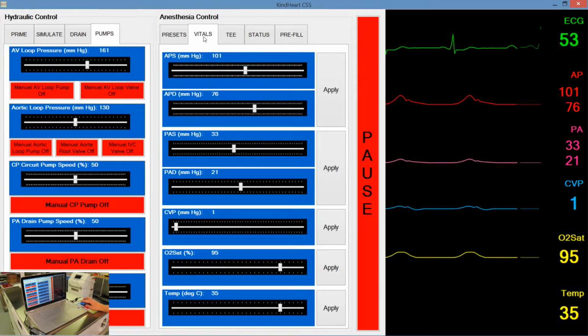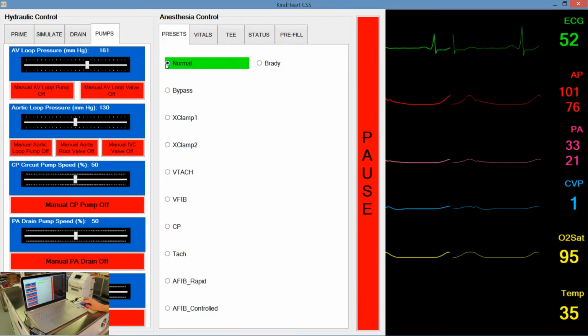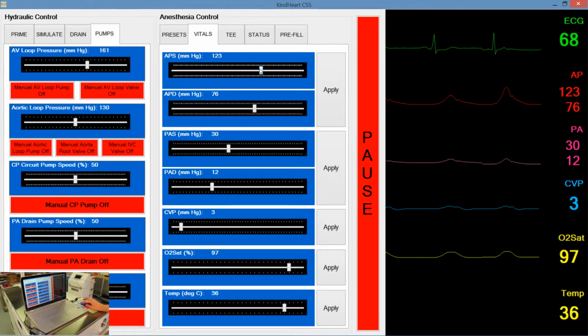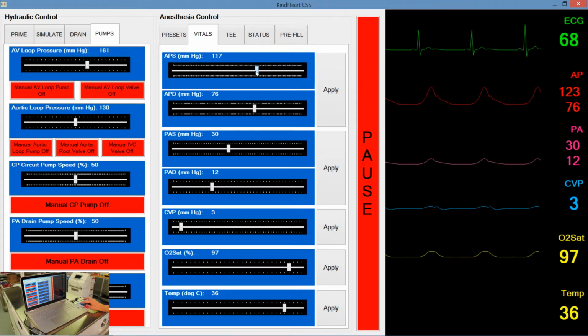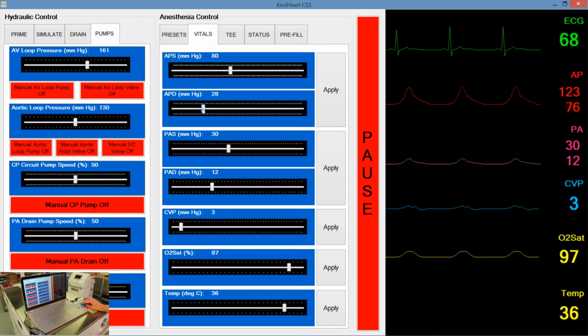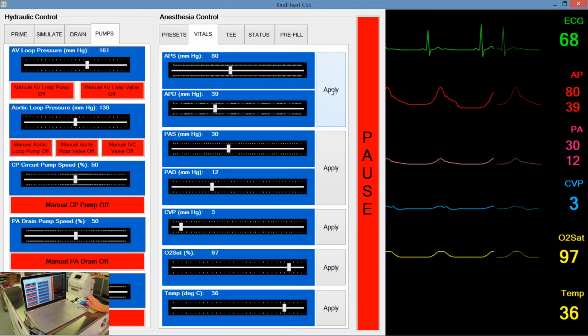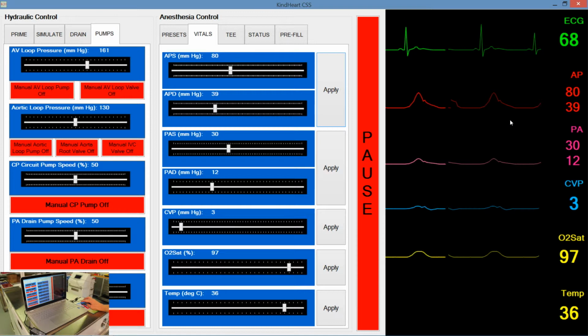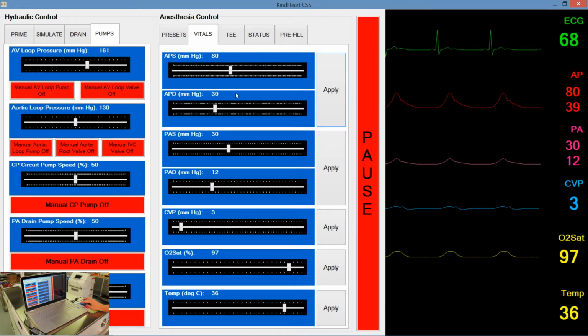When the vital signs tab is checked, what comes out of that, let me go back to presets and go back to normal. Back to vital signs. This vital sign number here for the aortic pressure systolic can be changed. For instance, if you wanted to simulate hypotension, you could move the systolic pressure down to 80, the diastolic pressure down to, call it 39. You have to hit apply, but when I hit apply, watch what happens over here on the vital sign screen. Once the device has a chance to internally reset, the pressure will be represented as lower than it was. That is part of the instructional capability of this machine.